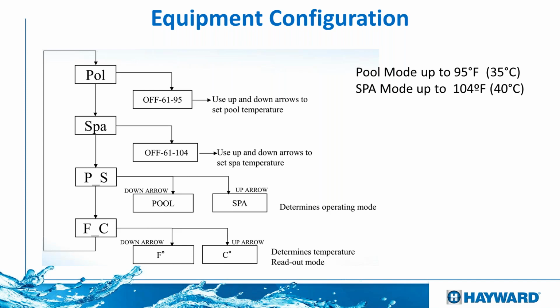This is for safety. You don't want somebody to go and raise the temperature up to 104, and then later on in the week you realize that your pool is actually a spa. It's really, really hot, and you wasted a lot of energy, or in the case of a gas heater, you wasted a lot of gas. So from the factory, we said that the maximum the pool can get is 95 degrees. If you want hotter than that, then you can go to spa mode and you can go up to 104 degrees Fahrenheit, which is 40 Celsius.